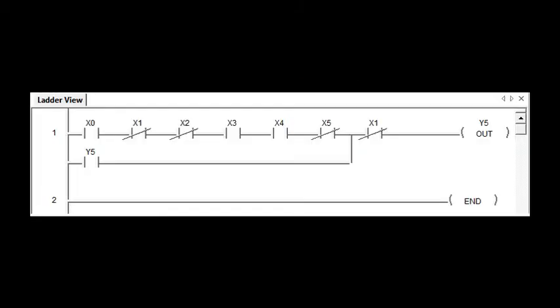I'll explain this program a little bit more. There are two kinds of input statements, a normally open contact and a normally closed contact. They're associated with the six switches. The important part about this demonstration is the effect that each switch has on the program. Whether each statement becomes true or false depends on what kind of switch it is, whether it's a normally open switch or a normally closed switch. That's independent from the type of programming statement that it is, normally open or normally closed. They do not have to match.